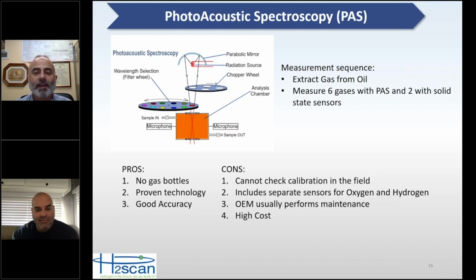So you do need to extract the gas from the oil, and photoacoustics measures 6 of the hydrocarbon gases. The 2 gases it does not monitor are oxygen and hydrogen, and so photoacoustic monitors have separate sensors for oxygen and hydrogen. So the pros here are there are no gas bottles. You don't need to check the calibration on the photoacoustic gases regularly. It is a proven technology, and you get very good and reliable accuracy from the photoacoustics.